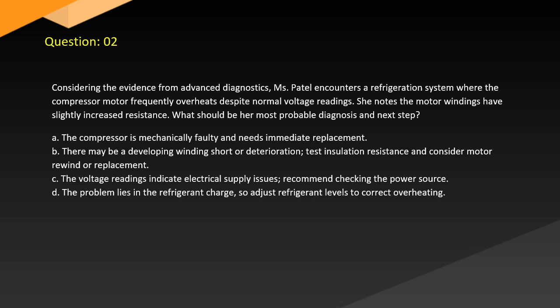A. The compressor is mechanically faulty and needs immediate replacement. B. There may be a developing winding short or deterioration. Test insulation resistance and consider motor rewind or replacement. C. The voltage readings indicate an electrical supply issue. Recommend checking the power source. D. The problem lies in the refrigerant charge, so adjust refrigerant levels to correct overheating.